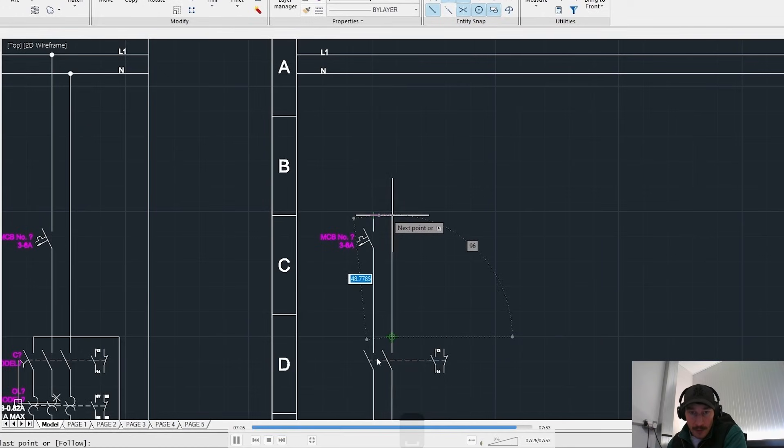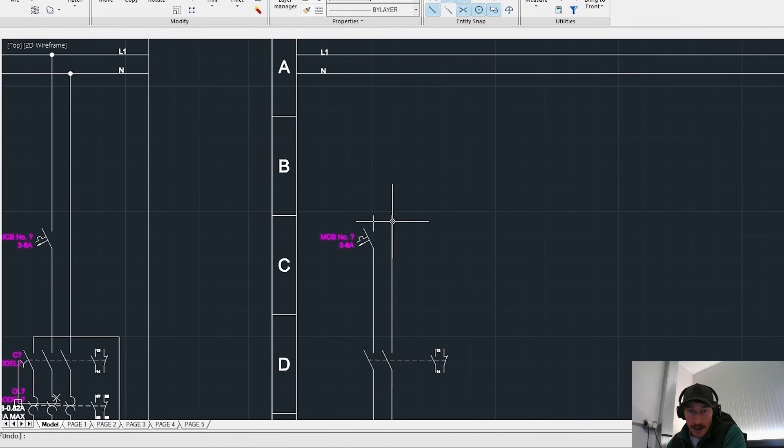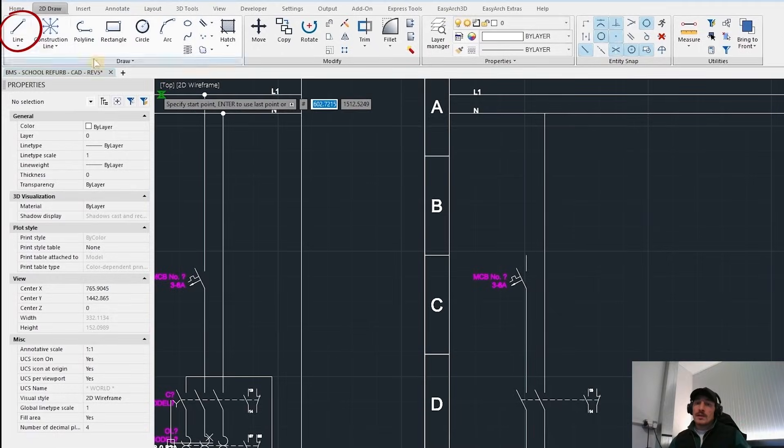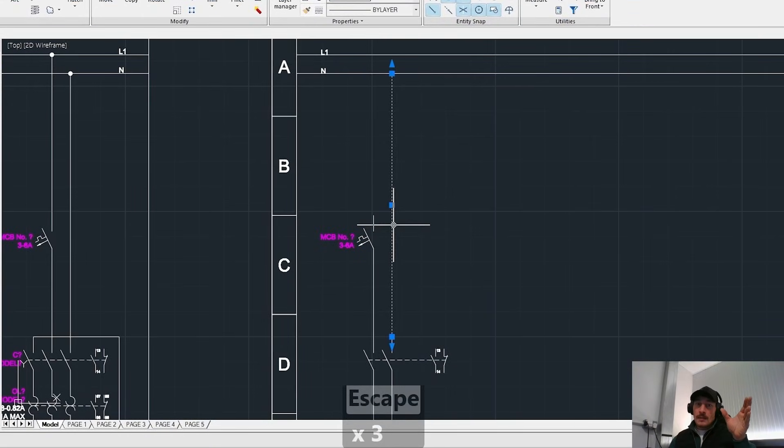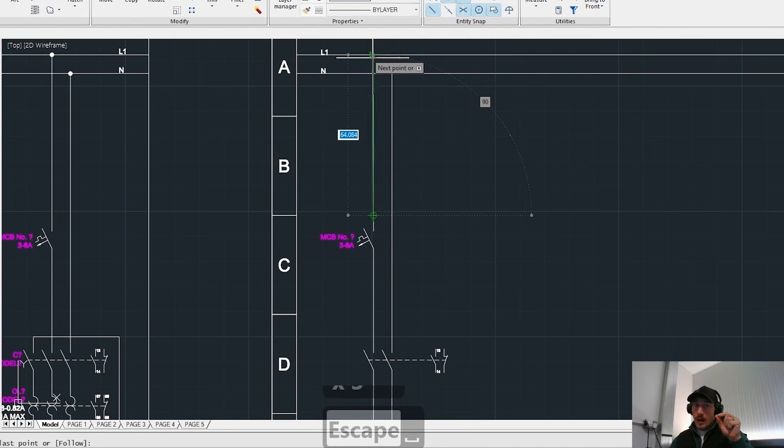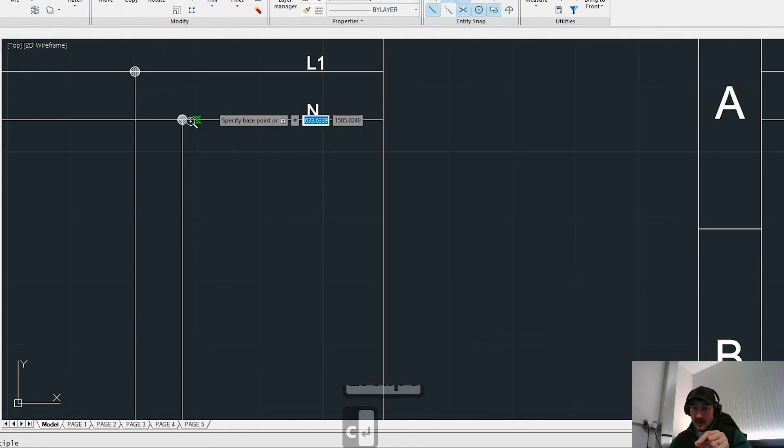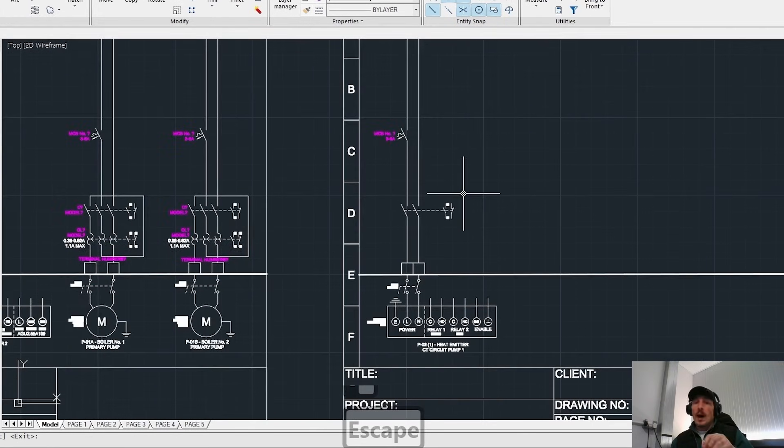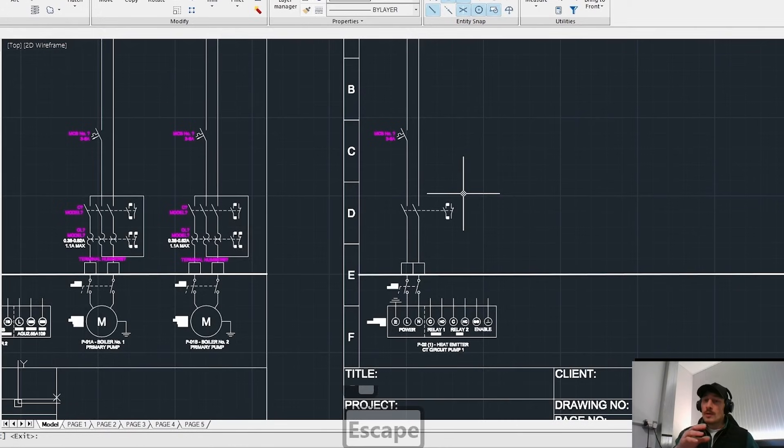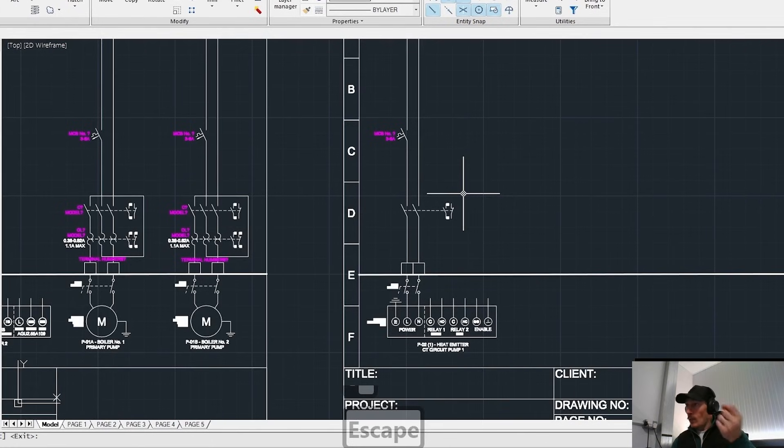I realize this later on. At the moment it looks like I'm putting this through a contactor when I don't think that's how it ended up. I think it just had constant main power supply and then the control was through the run enable signal. At the bottom right, where it says enable there. And that's controlled through a relay. So I think what you saw there wasn't entirely correct. It was just single phase, 230 volt AC to the pump, constant power via an MCB. So there was no contactor control. And then later on, I realised that the control is done through the run enable via a relay. So just to clear that up. I hope you enjoyed the video.